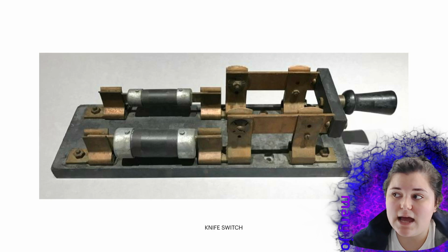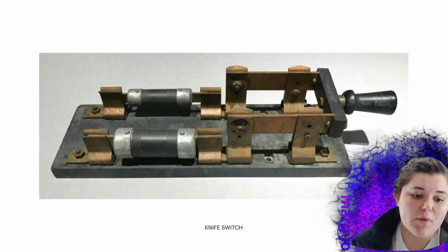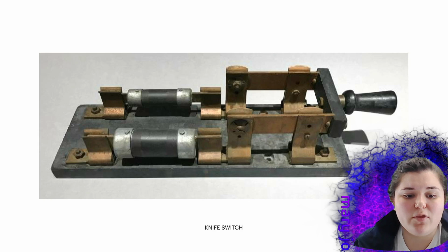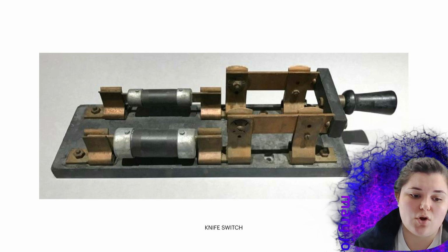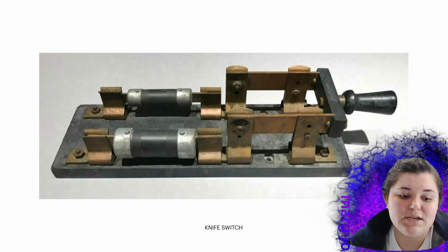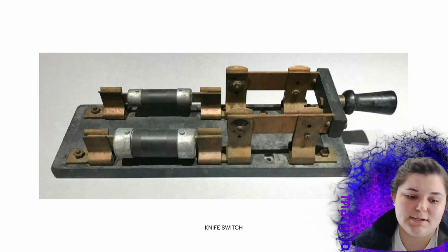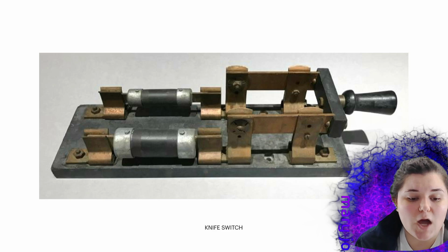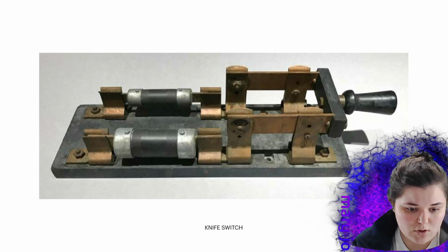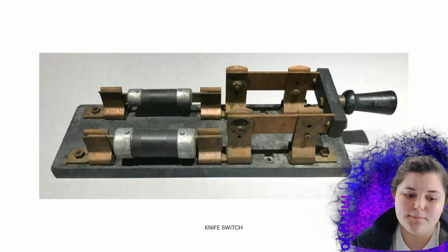So this is a knife switch. This is what used to be used in the industry. When motors were first introduced, they came up with a method called a knife switch to start and stop them. They were eventually discontinued for 3 reasons. First reason being, the open knife switch had exposed electrical parts, so that is a hazard, obviously. 2, the speed of the open-close mechanism was based on the operator.